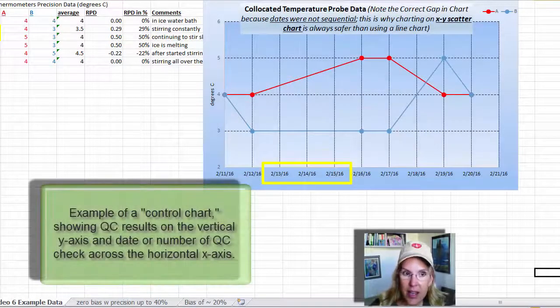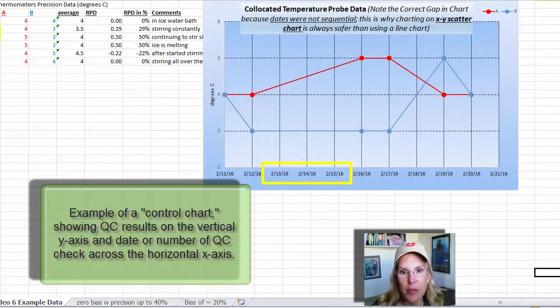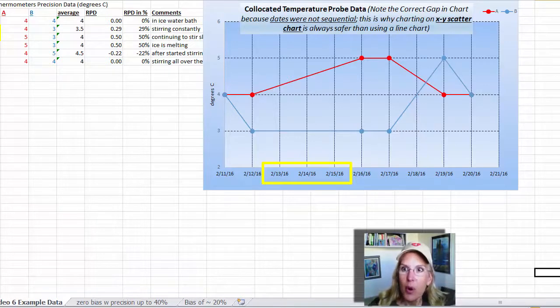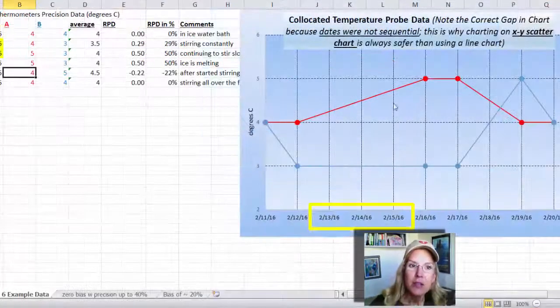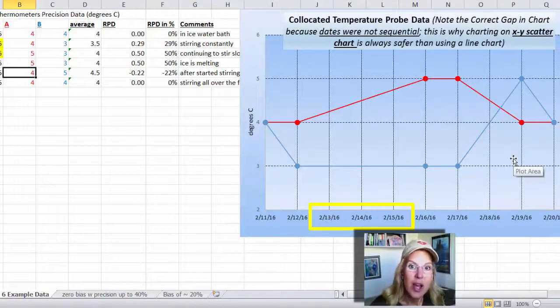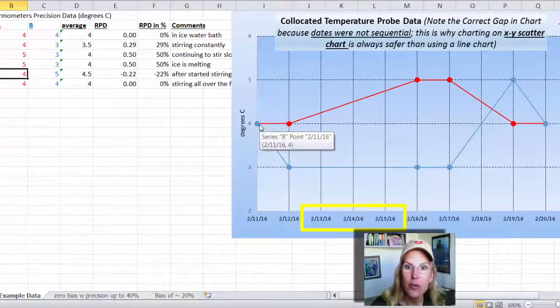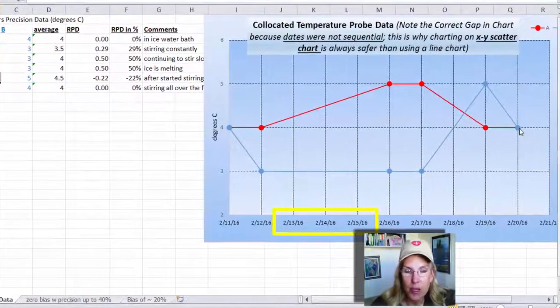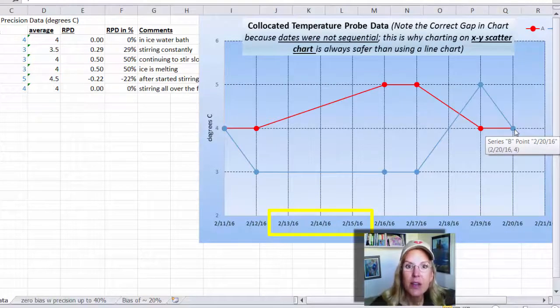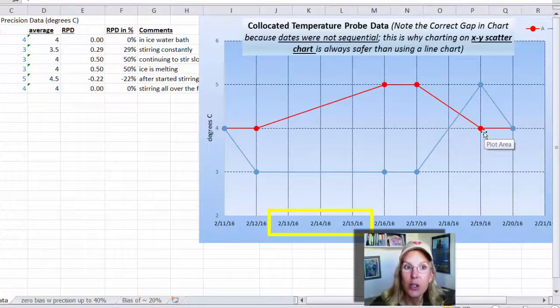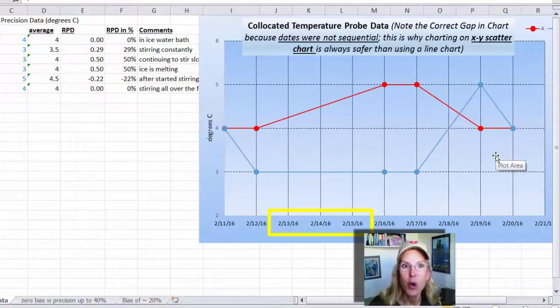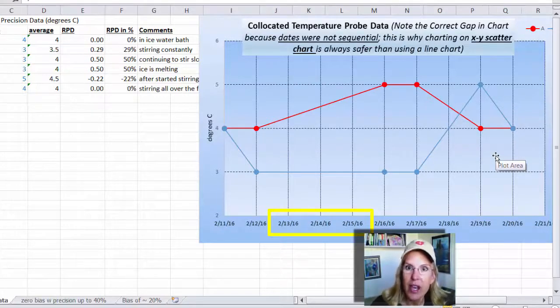This chart shows your data with the date along the x-axis. That's why this is called a control chart — you're looking at how well your system is in control at different times. You've got the data for temperature probe A in red. This data looks like there really isn't a consistent bias. At some points they're equal to one another — the first QC check and the last QC check, both temperature probes read exactly the same. In general, it looks like maybe probe A is higher, but then they switch, so I would say it's inconclusive as to whether these temperature probes have a bias.